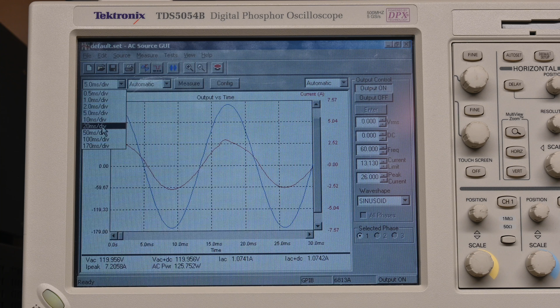Okay, so I'm going to close this. So there is the inrush current of a Dynaco MK3. If I lower the divisions here, this is what the current waveform is, the red waveform. So it's showing peak amperage is 7.2 amps, and then AC current 1 amp, 125 watts. This is 120 volts.